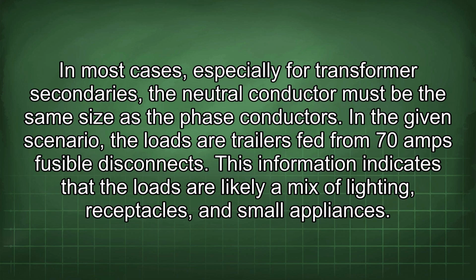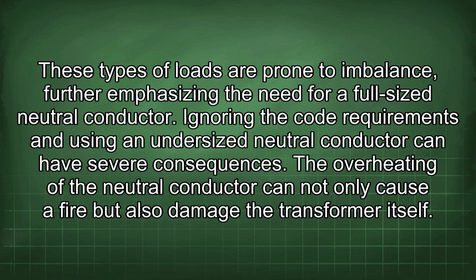In the given scenario, the loads are trailers fed from 70 amp fusible disconnects. This information indicates that the loads are likely a mix of lighting, receptacles, and small appliances. These types of loads are prone to imbalance, further emphasizing the need for a full-sized neutral conductor. Ignoring the code requirements and using an undersized neutral conductor can have severe consequences.